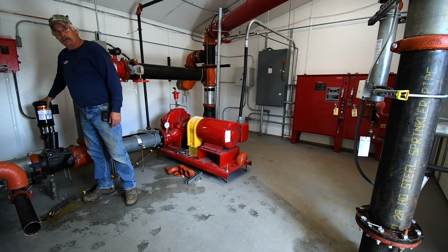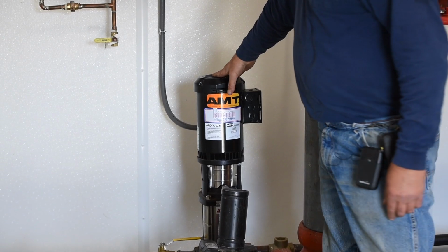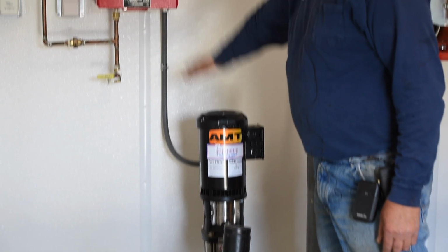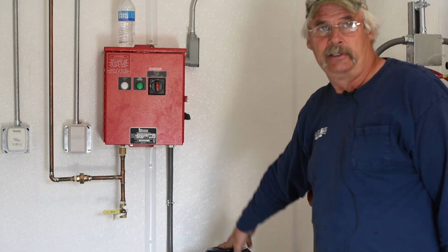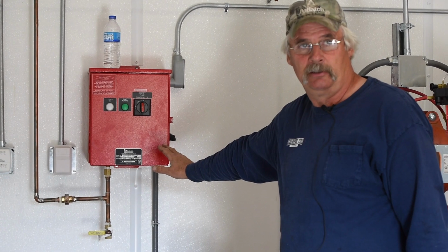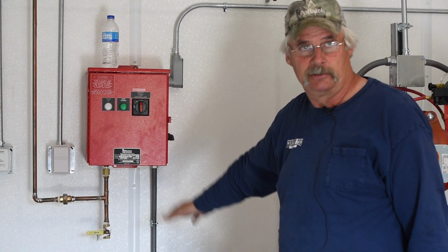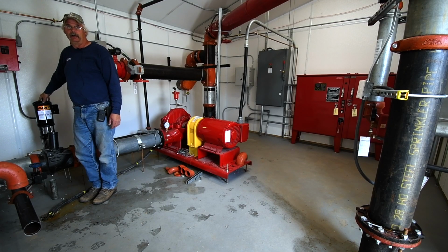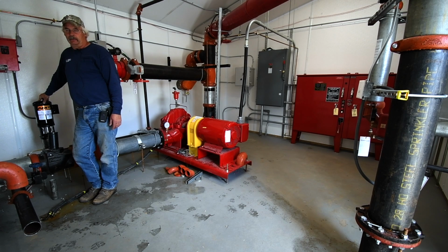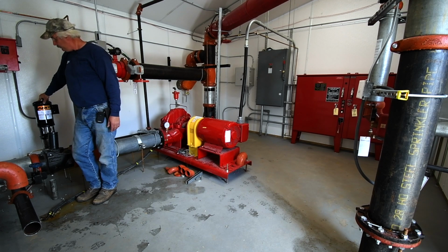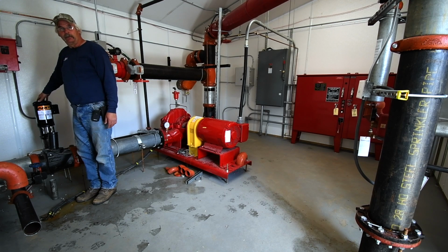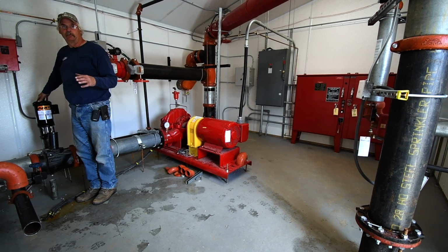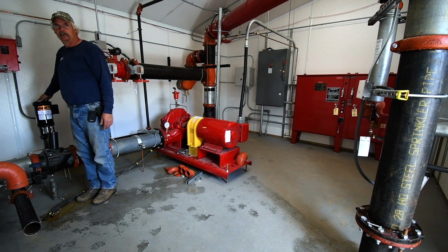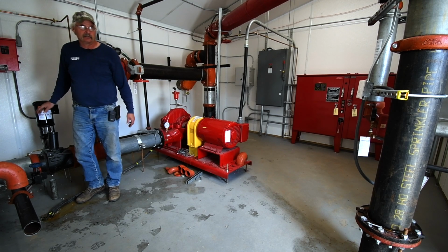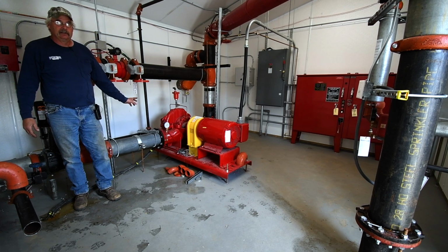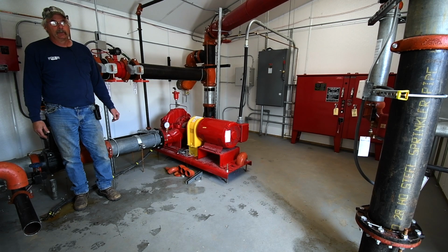This is a small pump. This is called a jockey pump. The jockey pump has its own controller here. Again, all these switches and devices will be left in an on position. They don't need to be turned on or off during a fire. They're automatic. So a drop of pressure, jockey pump will kick on, keep your system up to pressure. Once it can't keep up to that desired pressure, there's sensing lines tied to the fire pump that'll kick on.